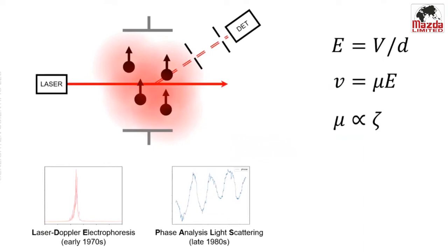As you increase the electrolyte concentration, you start to see adverse effects like heating or bubble formation at the surfaces of the electrodes and other unwanted behavior that makes the measurement impossible using the laser Doppler method. Phase analysis gets around some of the limitations, but sacrifices the ability to show you the distribution. Instead, you get a single average value.